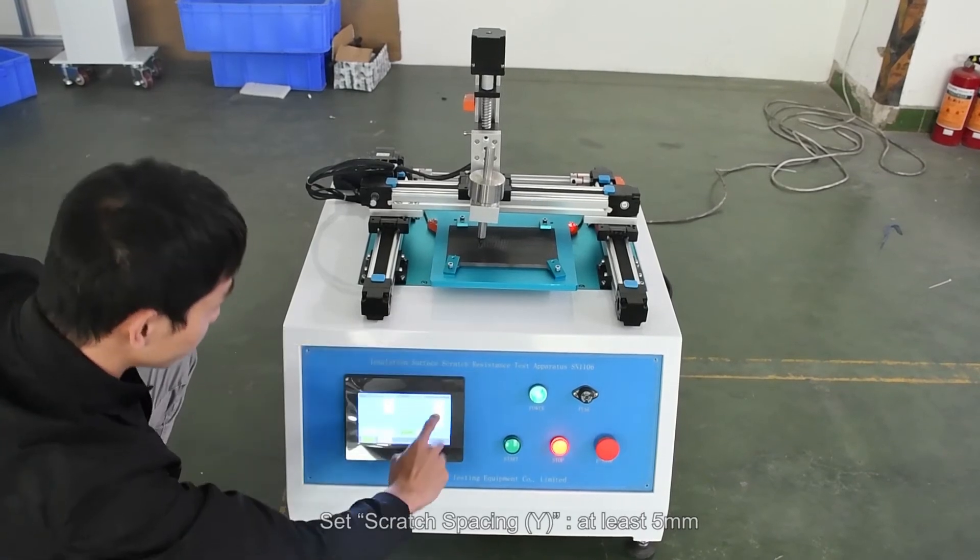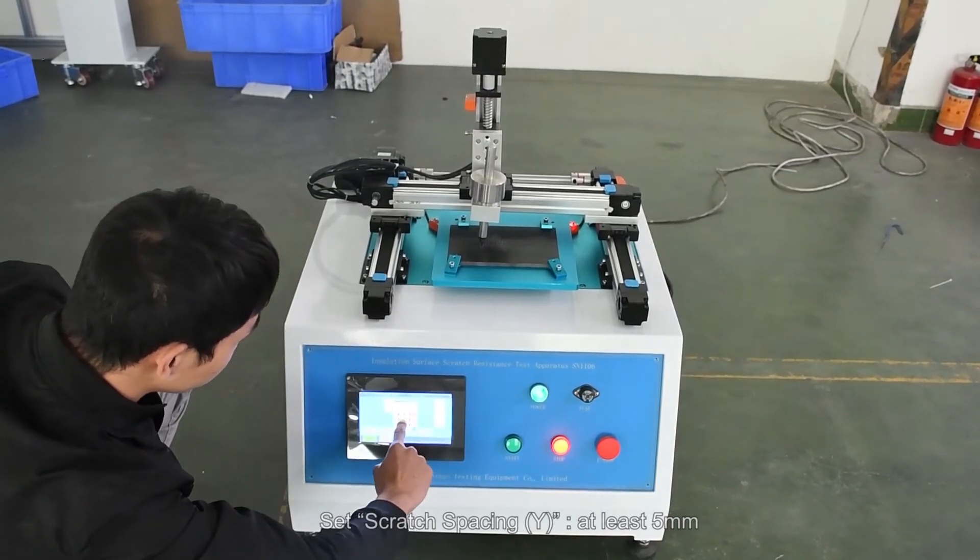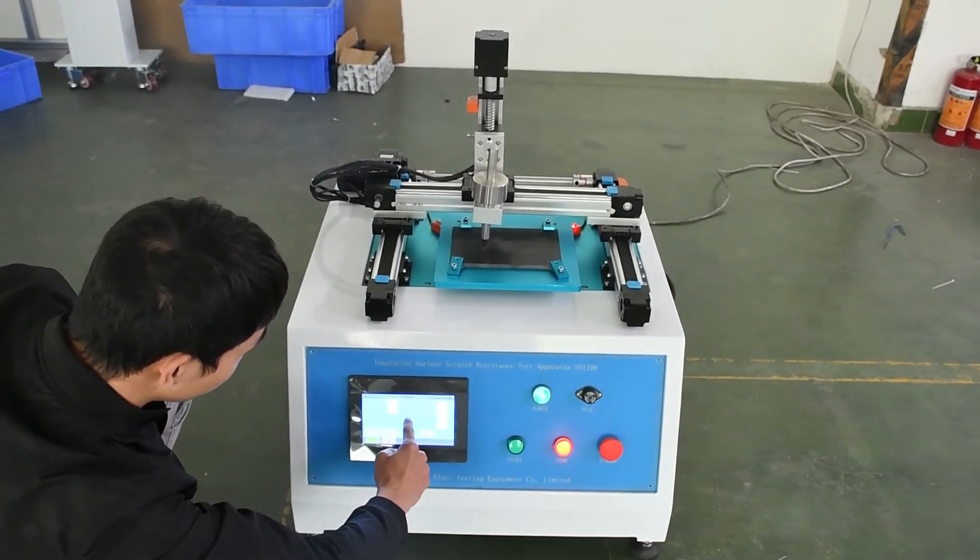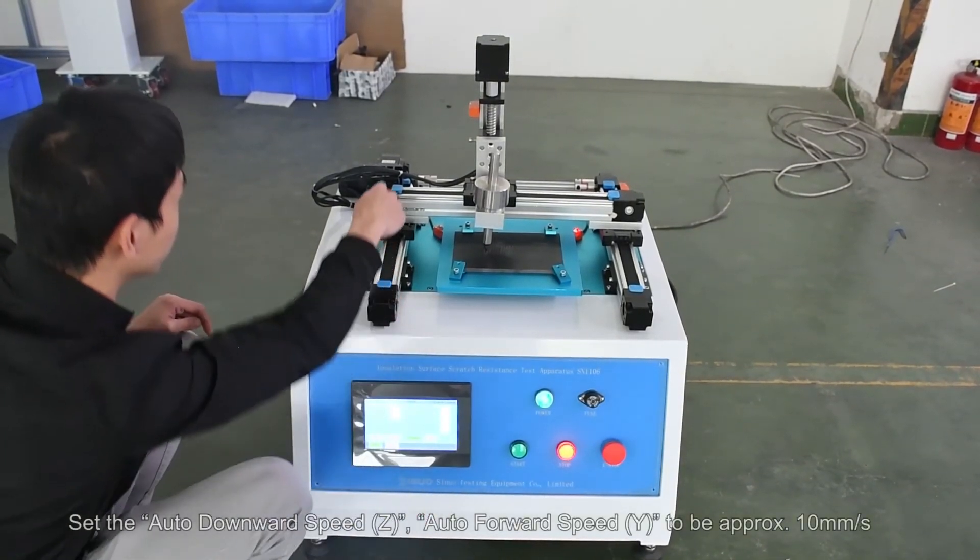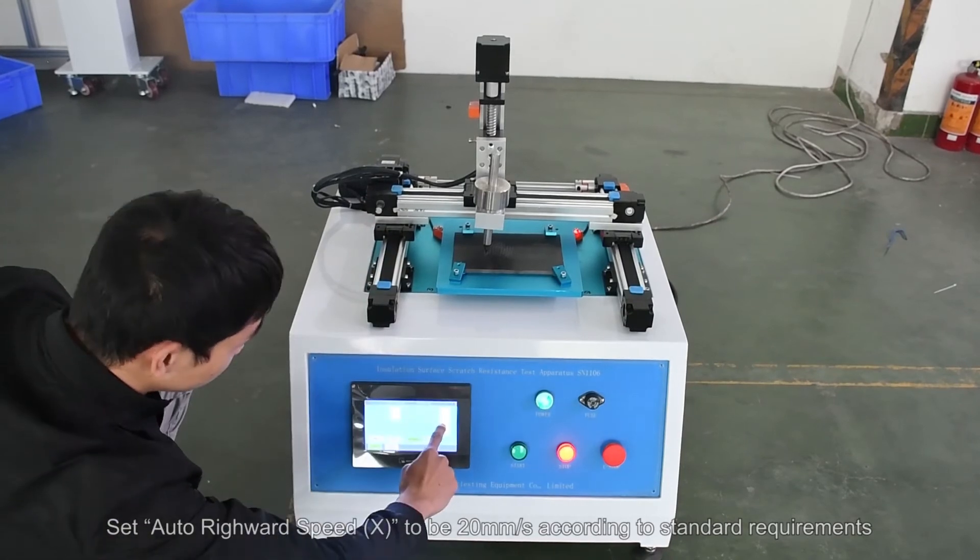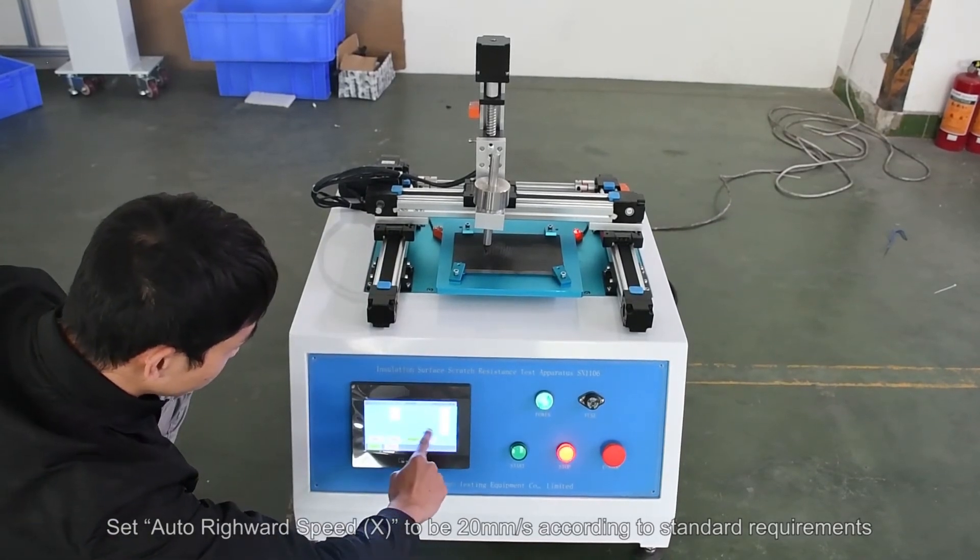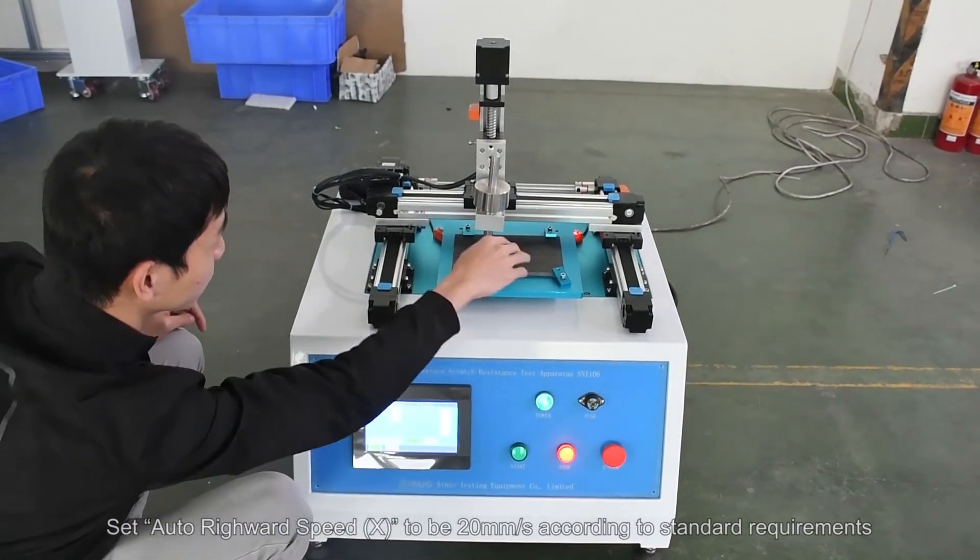Set scratch spacing Y at least five millimeters. Set the auto downward speed Z and auto forward speed Y to be approximately 10 millimeters per second. Set auto rightward speed X to be 20 millimeters per second according to standard requirements.